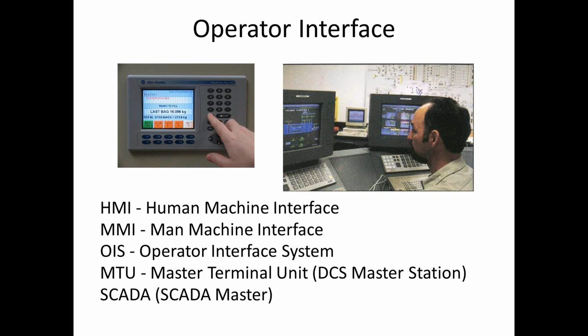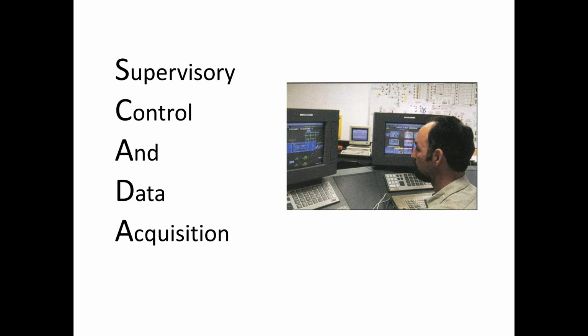The operator interface I'm most familiar with is the SCADA system, and it's probably the most prevalent in all of the treatment plants. And we'll talk a little bit about the SCADA system. SCADA stands for Supervisory Control and Data Acquisition. The supervisory part of the SCADA system basically lets you observe what's going on in the process. As I said, if you needed to take manual control, you could do that through the control system. But otherwise, you're basically letting a PLC do all the work.